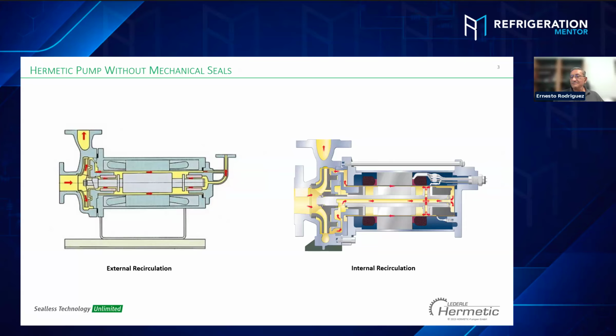We don't have any mechanical seals on this pump. We have two different designs: external recirculation and internal recirculation. External recirculation is a very good design, very good engineering. The only difference is we have the suction of the pump and the discharge of the pump, and part of the fluid goes through to the rear of the pump to cool and lubricate the pump. Internal circulation is basically everything internal. We don't have any external piping to cool and lubricate the pump. Basically, it's internal; you can see everything is inside.